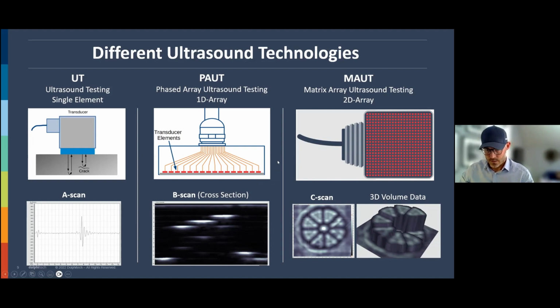Then a few decades ago, in the 60s, 70s, people started using what we call phased array or 1D array. This was really introduced to the market in the late 90s, maybe early 2000s, where they put a lot of these transducer elements next to each other. You can imagine this transducer on the left here, you put many of them next to each other. Of course, they're a little bit smaller. And then you get many, many A scans in a row. If you flip these A scans and put them next to each other here, as in a B scan, this is a B scan of 128 A scans. Then you can say that a high value of the A scan gives you a white color, and a low value gives you a black color. And then all of a sudden you have a cross section. So this is easier to interpret. It's a slice through material, and you can easily see where the cracks are and so on.